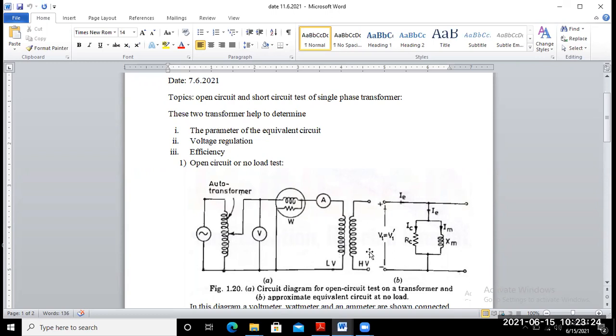Whatever the rating of the HV winding, we just vary 2 to 12%. That means up to 12% we are able to circulate rated current in the HV as well as the LV winding. So the maximum position will go to 2 to 12%. It is not that we apply the rated voltage of the HV coil, that means HV winding, on the HV side. When you change the voltage reading with the help of this auto transformer, you must be careful when the rated current flows. You just find out the rated current of the transformer.